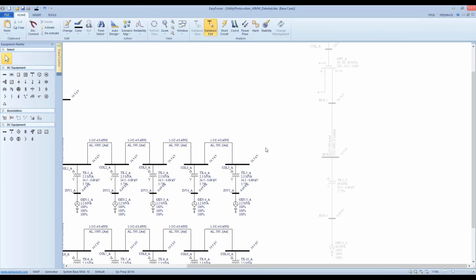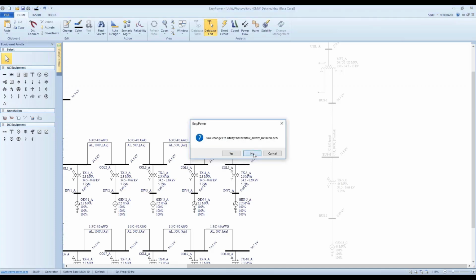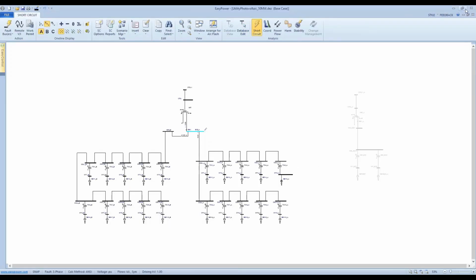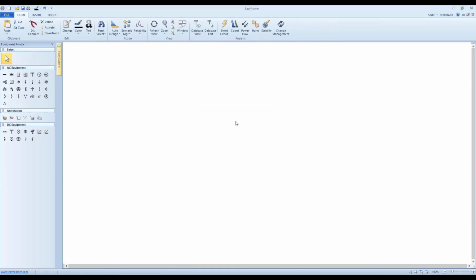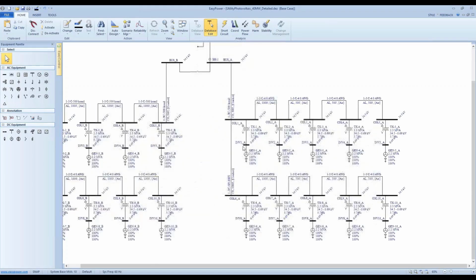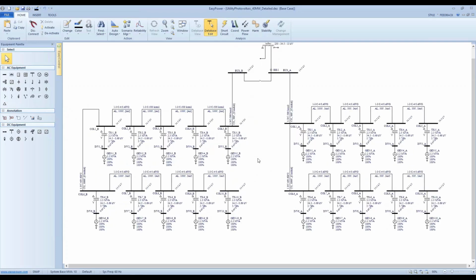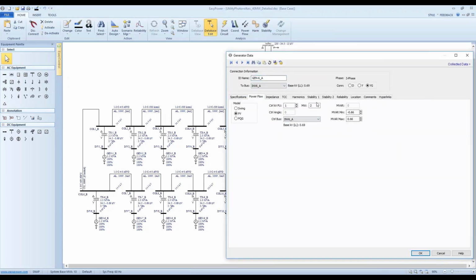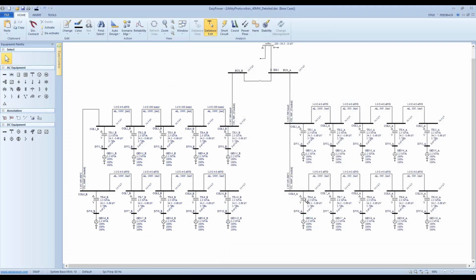Oh, I already have it open. Sorry about that, I should have this closed. I don't want to change anything. I need to close this as well. Okay, so let's edit it. Now this is my one-line design, nothing else. In this one-line design, I have 20 inverters, each of them rated at 2.2 MVA with 2 megawatts of generating active power. And I have my GSUs and my collector system.